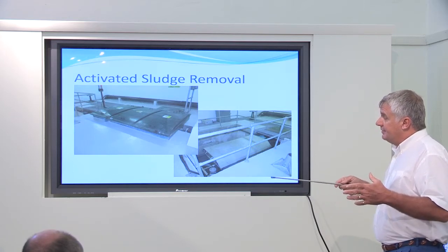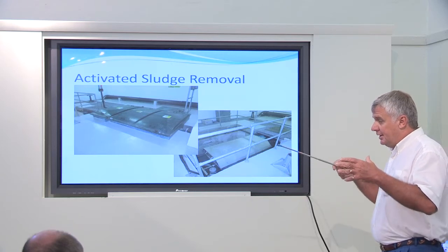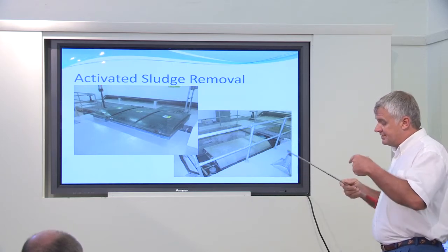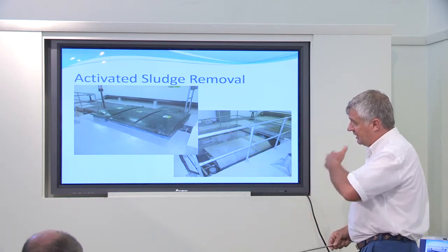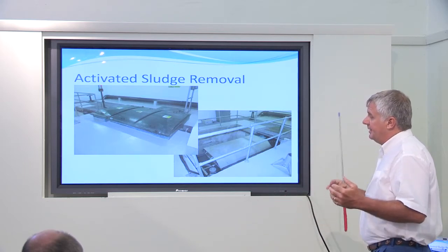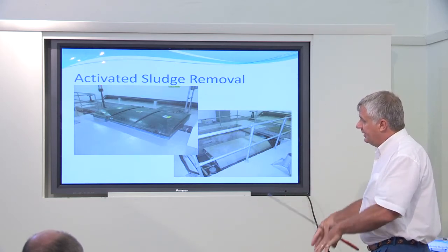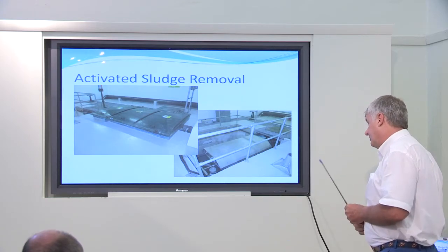that give the water stream a chance to slow down, and it's that slowing down that allows the solids to drop out slowly, and that's done in these things. They're effectively large tanks with sliding or sloped plates in them, and the sludge just settles on them, goes to the bottom, and then it's pumped off to join the sludge that we talked about previously.